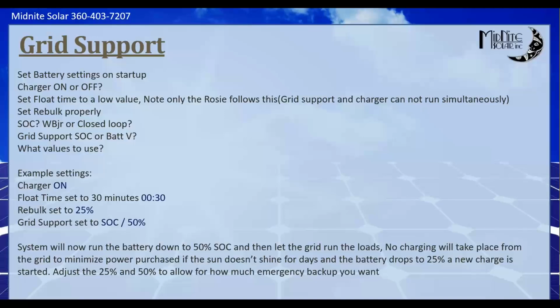And then set your rebulk properly — this is if you're going to use the charger. So step 2: if the charger is off, you don't really care about rebulk, but if the charger's on, you do. In my case, rebulk is set for right around 25% of my lithium batteries, and that seems to work really well. Then you have to decide if you're doing state-of-charge-based or voltage-based grid support.